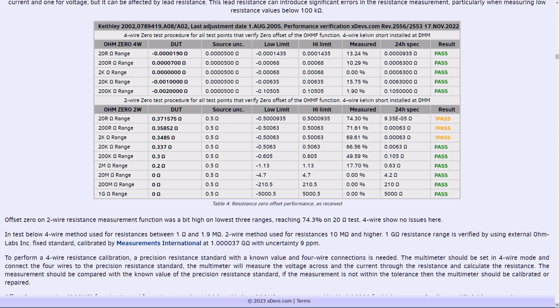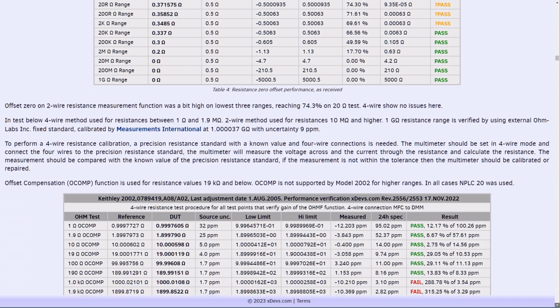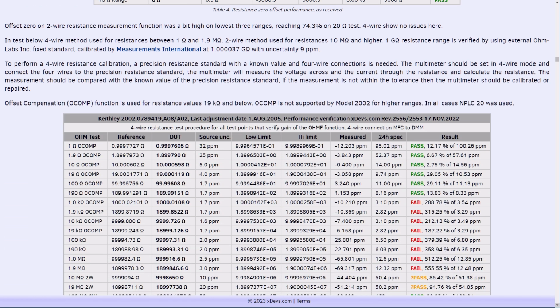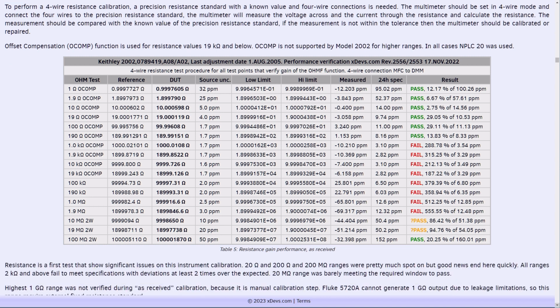Now the next step is to verify all resistance functionality with the gain errors on each range. This is done with the Fluke 5720A calibrator configured to source 17 fixed resistances from 1 ohm to 100 mega ohm. 1 gigaohm was not tested here because the 5720 cannot source resistances this high. And here we have solid failures for everything above the 200 ohm range. The 20 mega ohm range is barely meeting requirements.